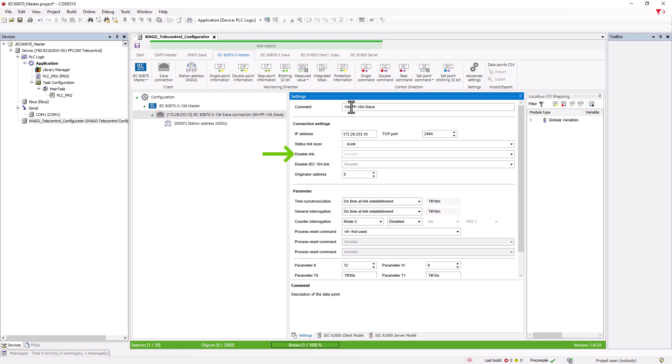The difference between the two is that with disable link, the TCP connection is completely switched off. With disable IEC 104 link, the communication is set to passive by sending the stop DT telegram and only the data transfer is deactivated, but test telegrams are still sent. This option is often used for redundant links. It allows the link to be switched to passive, but it is still monitored.